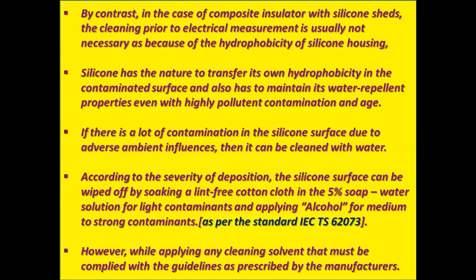Again, I repeat, according to the severity of deposition, the silicone surface can be wiped off by soaking a lint-free cloth in the 5% soap water solution for light contaminants and applying alcohol for medium to strong contaminants, as per the standard IEC TS 62073. However, while applying any cleaning solvent, that must comply with the guidelines as prescribed by the manufacturers.